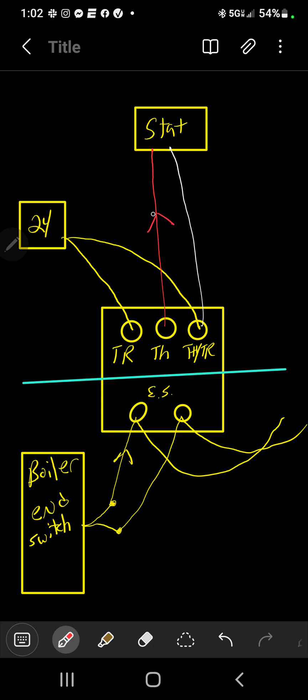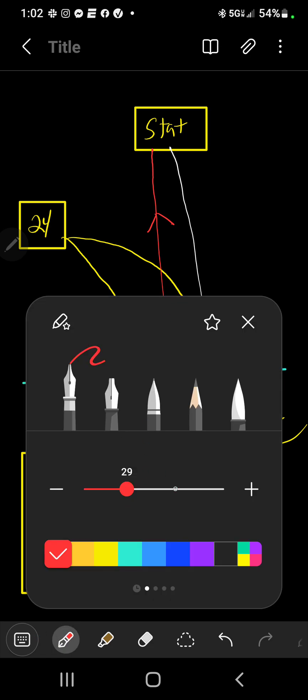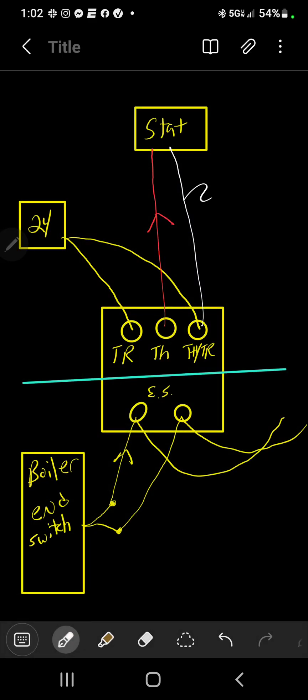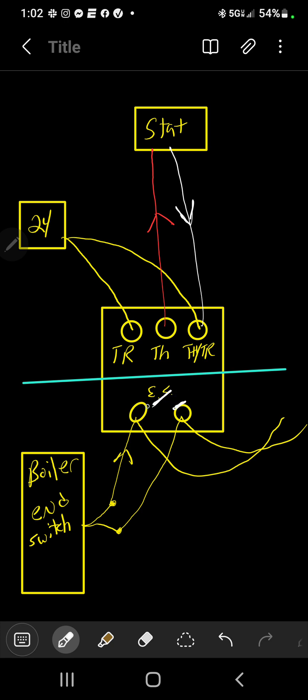Now once you get a call from your thermostat for heat, then it sends the 24-volt signal back to this zone valve. Once it sends it back, the motor in the zone valve now opens. When the zone valve turns and opens, there's a switch right here. It's not connecting. Once it opens, this switch now closes the circuit. And now the voltage can come back to the boiler, so now the boiler turns on.